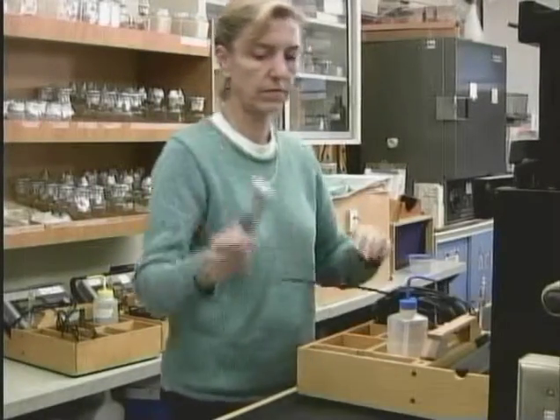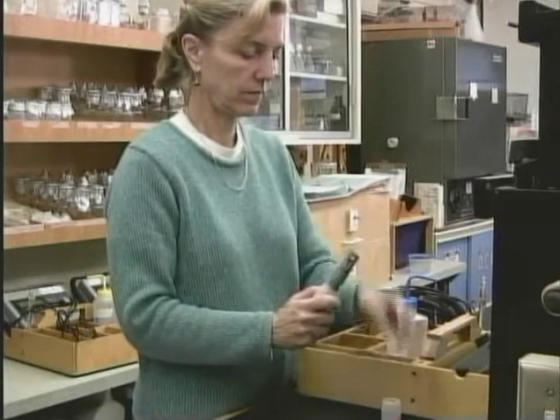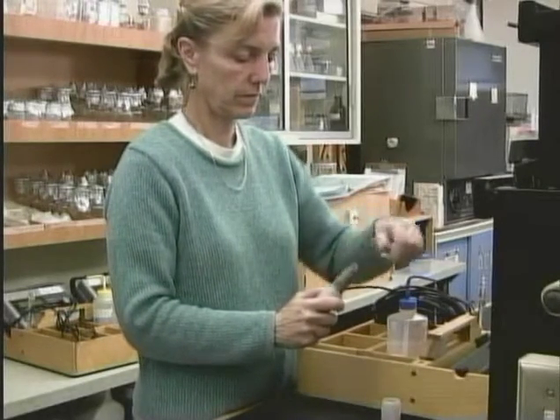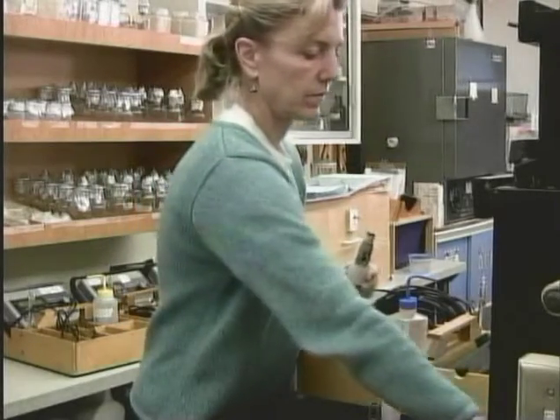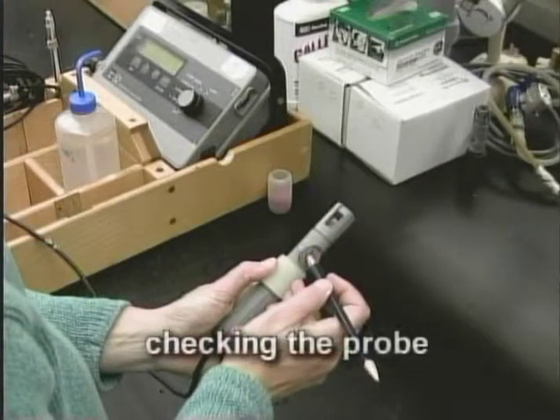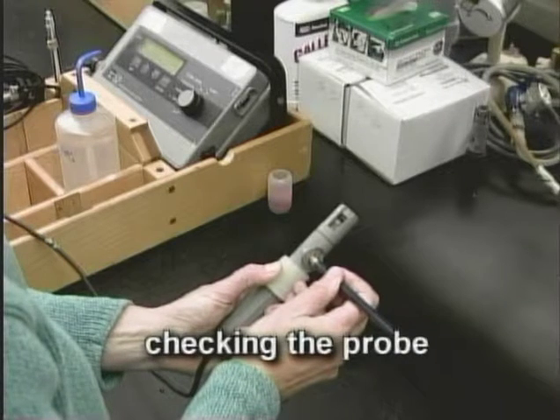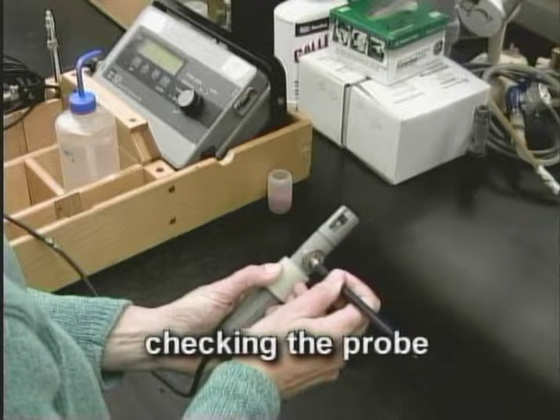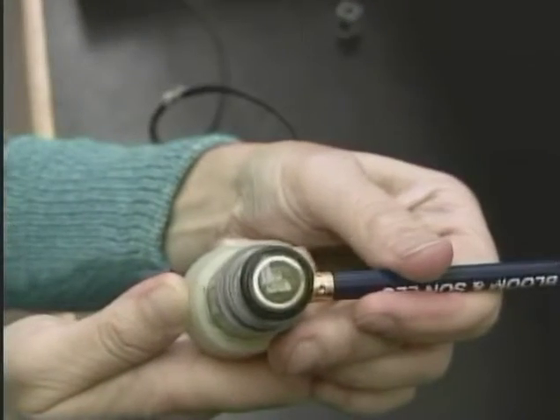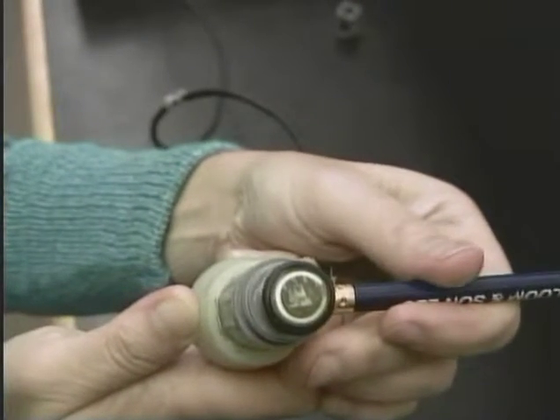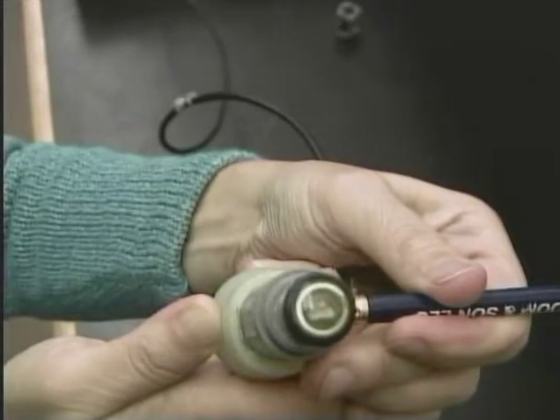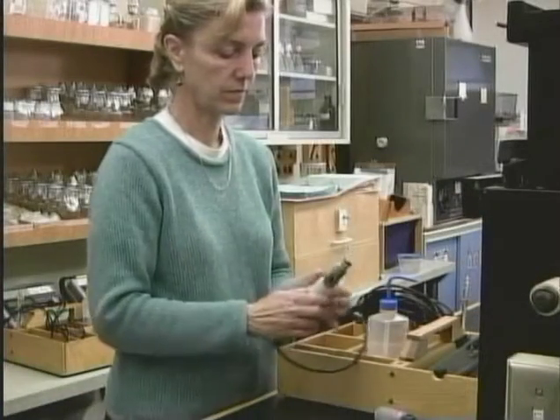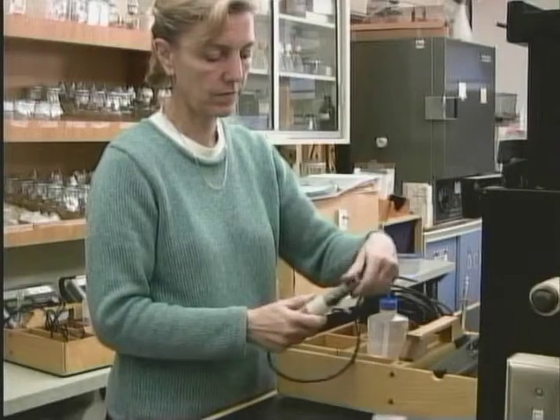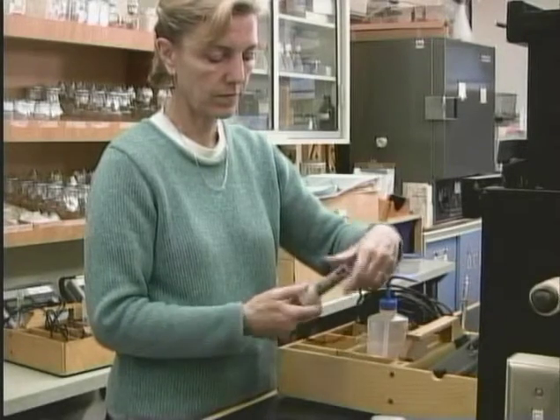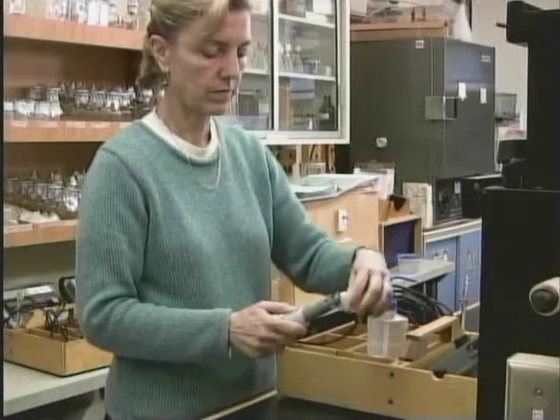Next, you'll want to check the probe for air bubbles under the membrane. Large air bubbles prevent the meter from working properly, and if not caught in time, cause your DO data to become inaccurate. Begin by removing the protective plastic covering from the end of the probe and observing the fluid electrolyte under the acetate membrane. It may be helpful to gently depress the pressure compensating membrane, the rubber disc, on the side of the probe a few times with the eraser end of a pencil. If air bubbles are present in the reservoir below the membrane, they usually rise to the underside of the surface of the membrane and become visible.